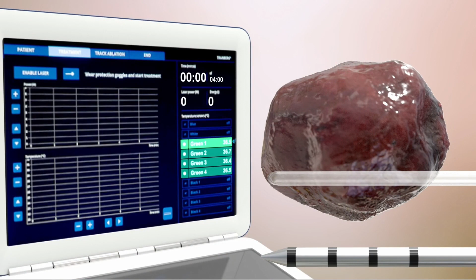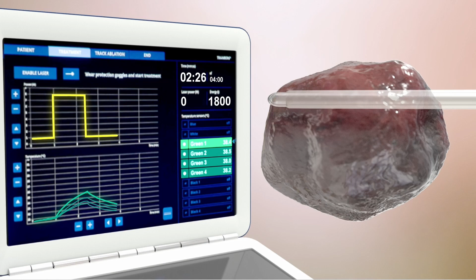Once applicator location is double-checked, the laser is activated and laser energy is applied to the target treatment area. Target temperatures are monitored in real time using the temperature probes. Instant cell death is achieved at 60 degrees Celsius. Upon completion of this individual treatment, the temperature probe and catheter with laser applicator are removed, and the process is repeated until all areas called for in the treatment plan are ablated. When the clinician is satisfied with the overall treatment, the ultrasound and any remaining accessories are removed, and the patient is allowed to recover.